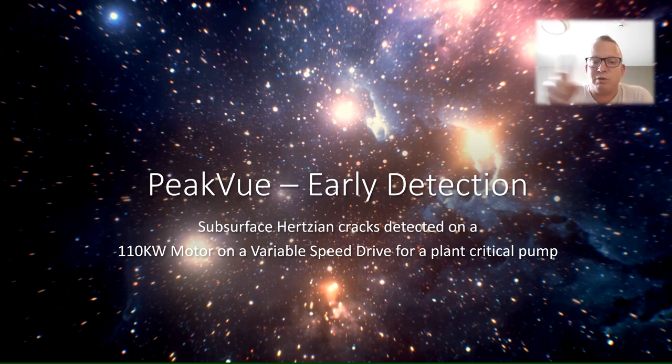So as the rolling element goes round, we've got a slight bit in the load zone, we get plastic deformation where the grease also goes solid, stops the metal hitting the metal, but the ball bearing and the metal sort of flex a little bit. So you get under subsurface, you get fatigue, so you get subsurface fatigue.